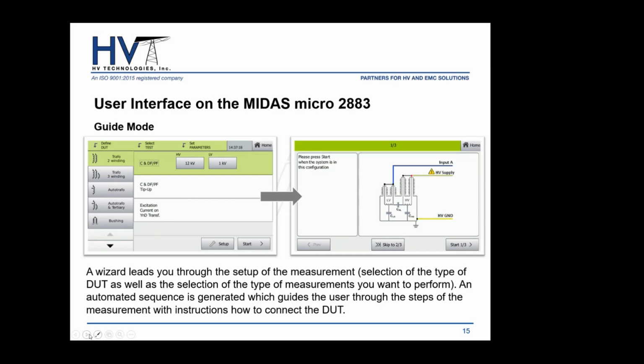Guided mode is probably my preferred mode. The guided mode is basically a wizard that'll lead you through the test setup of the measurement. It'll lead you through selection of the type of DUT, as well as the type of measurements you want to perform. When you define your device, whether it be a 2-winding transformer, a 3-winding transformer, or a bushing, it'll give you this sub menu, and you can choose what you want to test. If we wanted to do just capacitance and dissipation factor, we'll choose capacitance and dissipation factor. We'll set what our voltages will be for each winding, in this case for a 2-winding transformer. And then you can hit start.